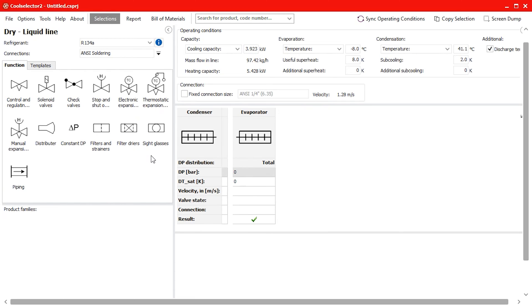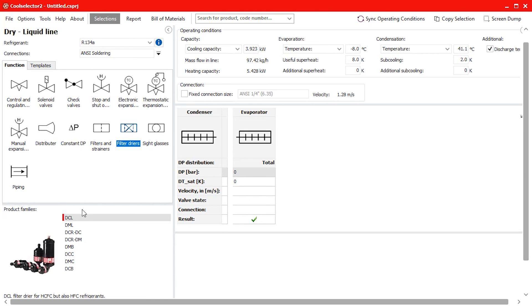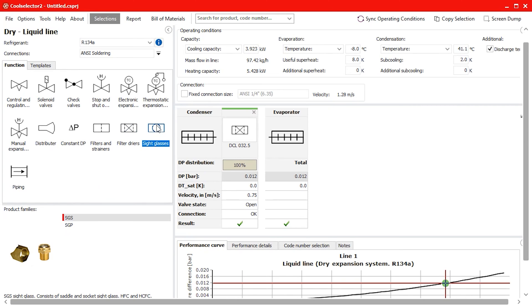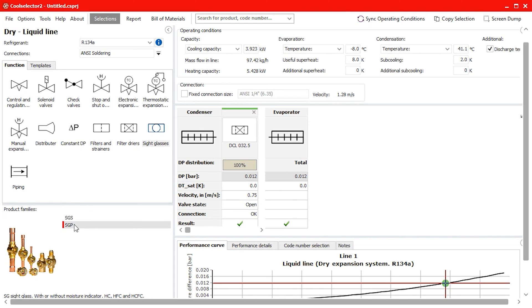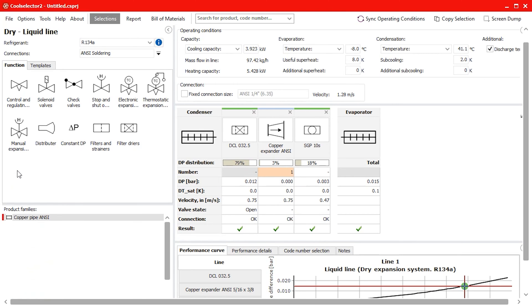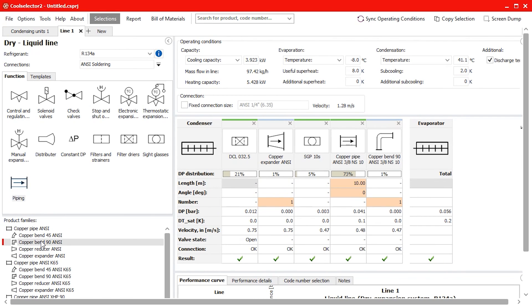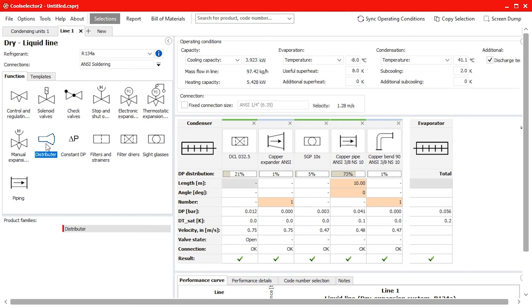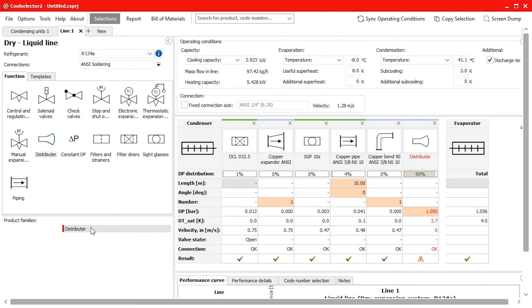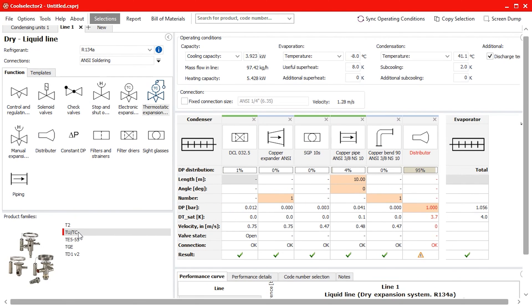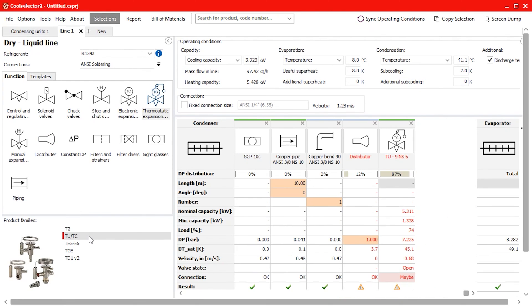We can then choose our connection type and for this example we will choose the ANSI soldering. Now we can add additional system components. I will add a filter dryer by double clicking the product family, in this case the DCL type and now it appears in the system diagram. Then I will add a sight glass, the SGP type for this example. Then I will select piping and add a straight pipe as well as a 90 degree bend. Now we will add a distributor to account for the pressure drop.